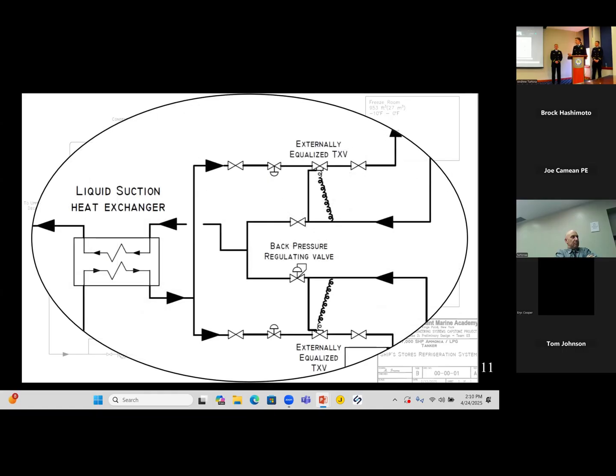Next, we're going to look at the right side of the drawing. As mentioned prior, we have our liquid suction heat exchanger. This is used to subcool the liquid refrigerant prior to entering the evaporator, as well as evaporate any leftover liquid refrigerant prior to entering the compressor. 2 externally equalized TXVs and a back pressure regulating valve on the chill box maintain humidity control within the refrigerated space.